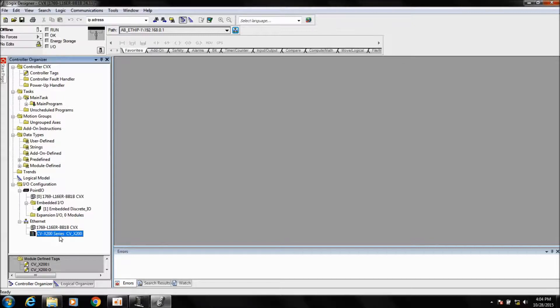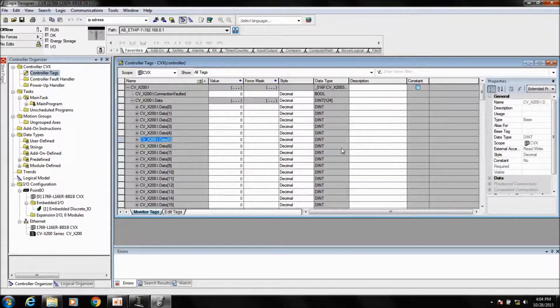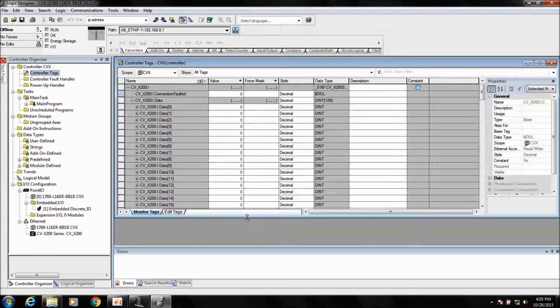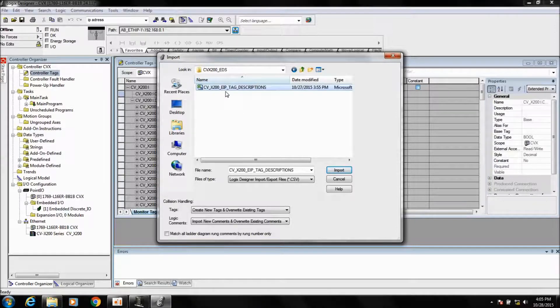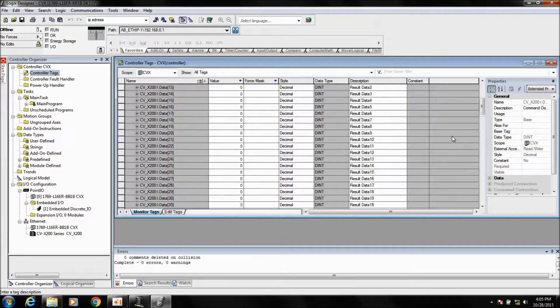The module has been added to the Ethernet section. In Controller Tags you can see it listed, but initially it appears as generic with no descriptions. Importing the EDS also adds a boolean Connection Faulted tag automatically. To add descriptions, go to the Tools menu and import the tags comment CSV file. Once imported, it automatically populates all the descriptions, making the data mapping easy to understand.